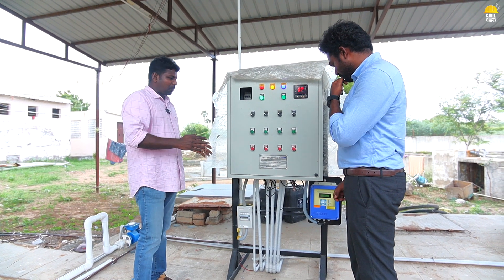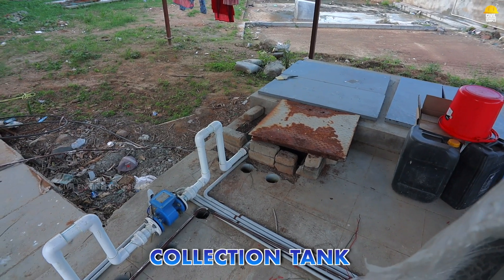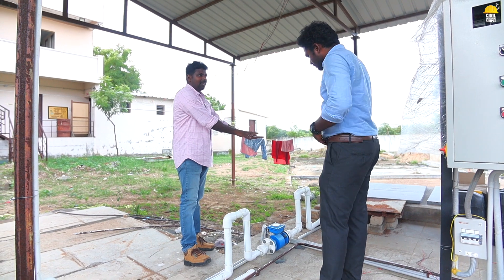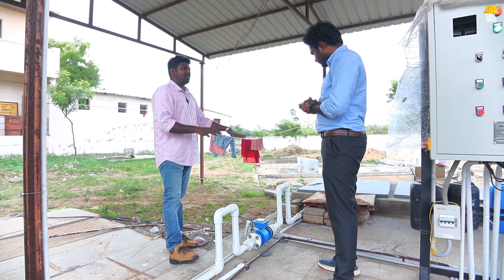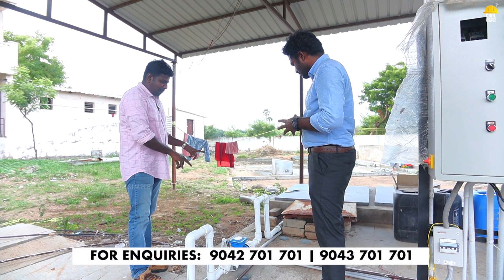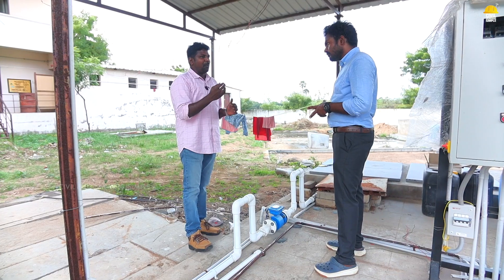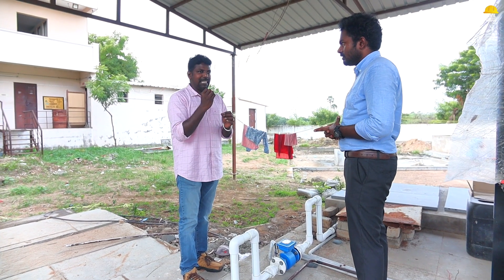This is our entry point — the sewage collection tank. This is the collection tank where all the water is collected. This is the storage. This is a submersible sewage pump with a flow meter sensor in the tank. When we pump the water over 24 hours, we pump at 100 liters per hour.